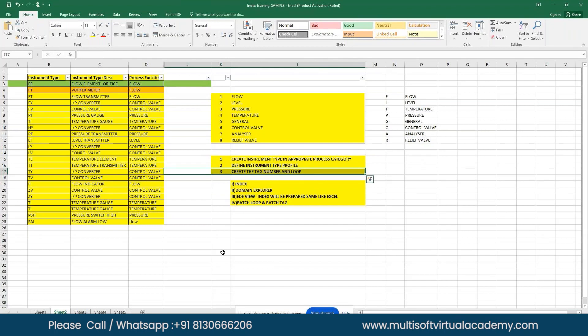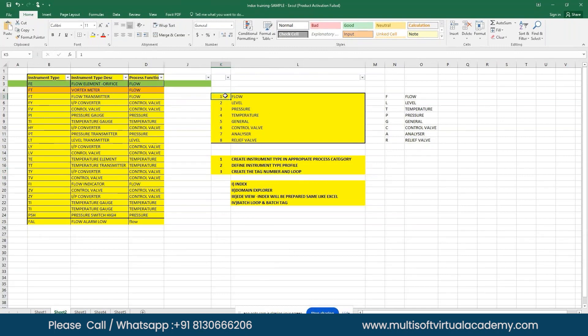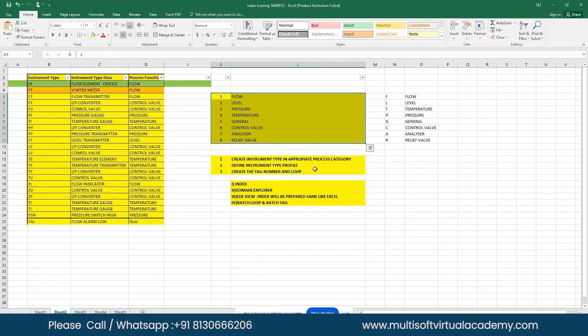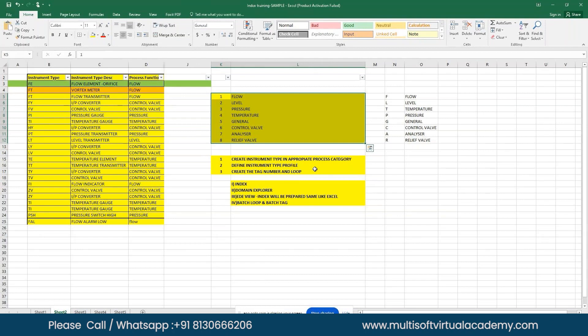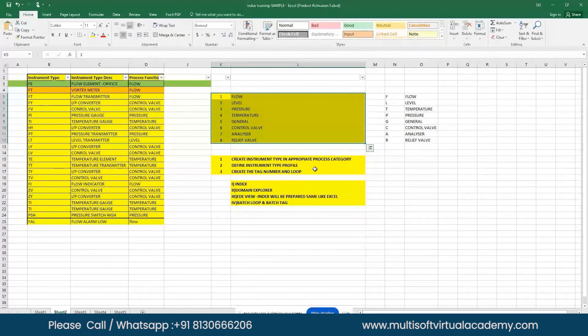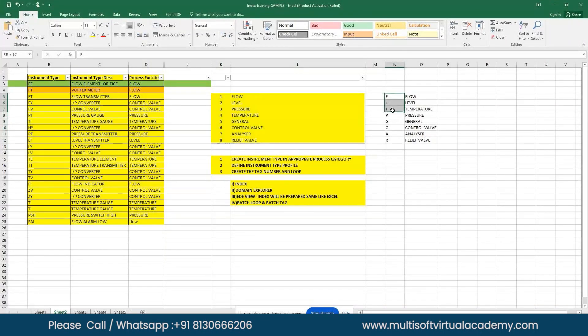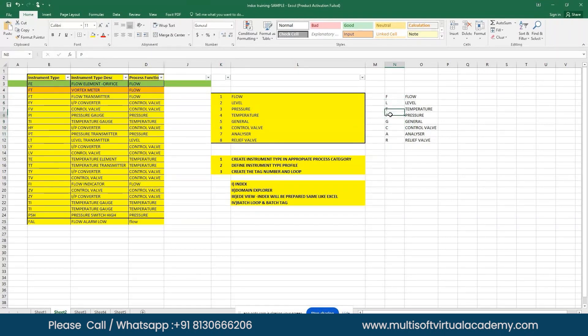Before preparing instrument index in SPI, you must know the process functions in SPI. In SPI we have eight different process functions. Normally as instrumentation engineers, we all knew the major process parameters: flow, level, temperature, pressure. Apart from that, in SPI there are four more parameters: general, control valve, analyzer, and relief valve. Including these four, there are a total of eight process functions which you need to memorize. The short way to learn quickly is FLTPGCAR: F-flow, L-level, T-temperature, P-pressure, G-general, C-control valve, A-analyzer, R-relief valve.